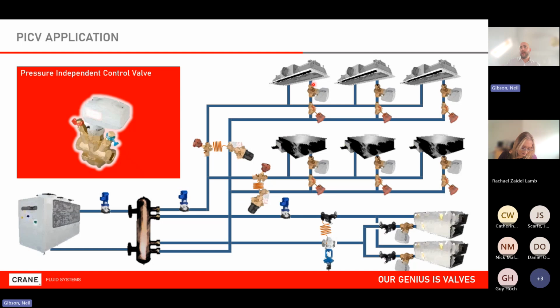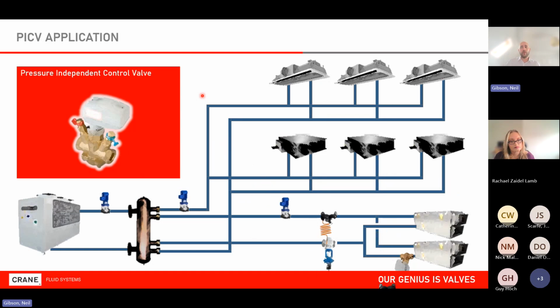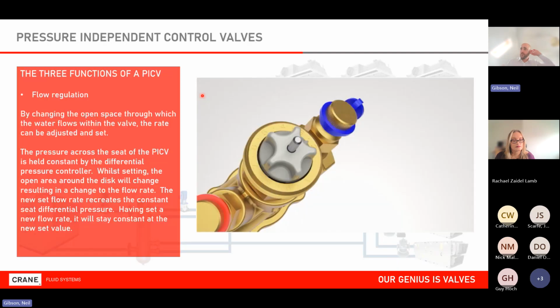We have a 2-port valve on every coil. We have a balancing valve on every coil, and we have some form of differential pressure protection on every branch. It could be somewhere else, but on every branch. The idea of a PICV is it removes all of those. We don't need them. They're not required, overcomplicated, costly, time-consuming, and we replace it with a single device. Now, a PICV has a diaphragm within the valve itself, so it can be pressure independent. It has a regulating feature, so it's my regulating valve, and I can screw an actuator on the top, so it's my 2-port valve as well. So it massively simplifies the system.